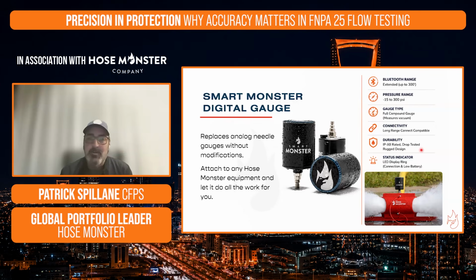And we also drop test these up to 10 feet. I know I've dropped a few of these myself, right? When you're working in that fire pump room, on that hard concrete floor, and you've got tools in your hand, sometimes they will drop on you. These really hold up to the challenge. It won't get damaged as it's a very rugged design. And then we also have an LED ring on each gauge that will show you the status of that gauge, show your connectivity, as well as if there are any issues with battery power or consumption.